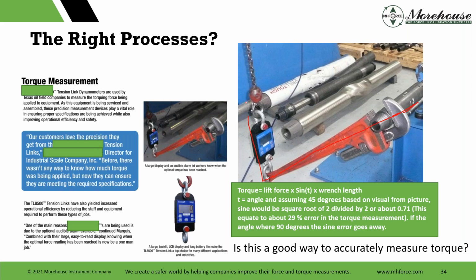No good whatsoever. If we think that angle is about 45 degrees, based on a visual from the picture, maybe it is, maybe it's not that bad. Though we can actually calculate what we would think the error would be. At 45 degrees, the sine would be the square root of 2 divided by 2, or about 0.71. And this equates to about a 29% error in the torque measurement.